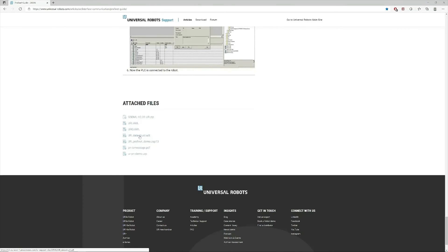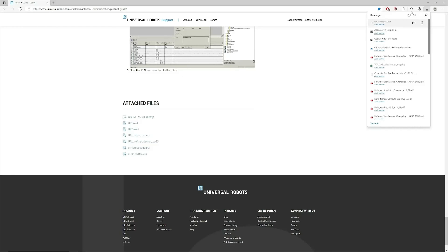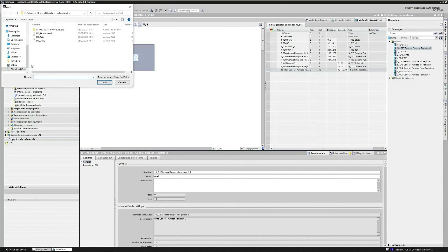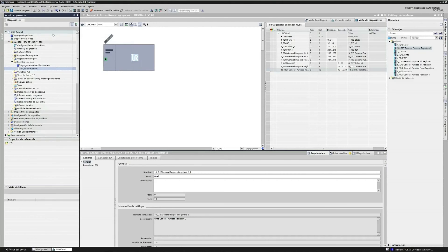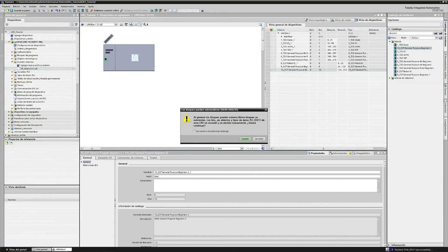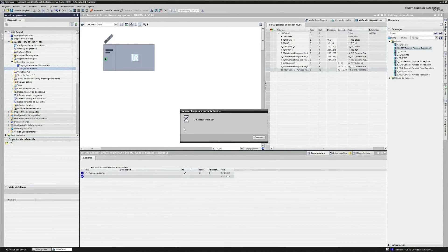We change the IP address and the name, and we download the files. In my case, I download the .udt because I have a 1500 series Siemens, but if you have the 200, 300, or 400 series, you will have to download both files as .awl. In external sources, we double click to add an external source file, then right click on the file and generate the blocks.